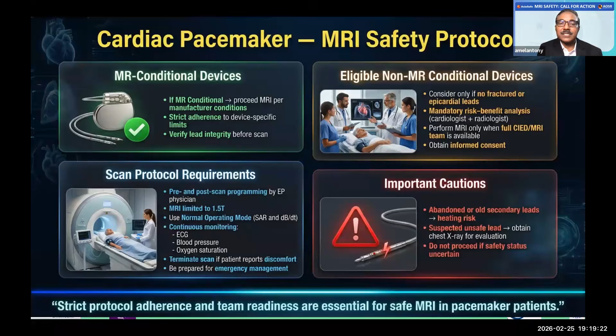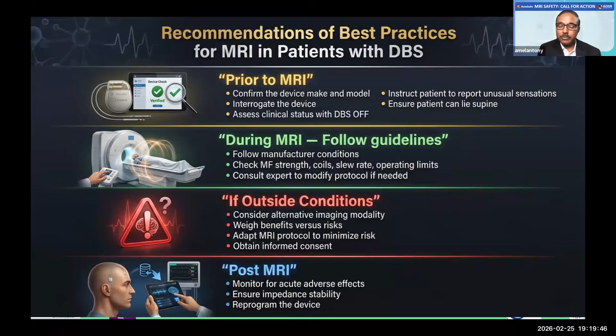And as mentioned again, if it is MR conditional, all the conditions specified by the vendor have to be met so that it's a safe scan for the patient as well as for the equipment. As far as DBS is concerned, the question always arises whether this particular scan is required, especially if it's the brain. Is there any other choice? And if it's for some other condition outside the brain, one should always consider an alternative imaging modality. And obviously one has to monitor for acute adverse effects and ensure that impedance stability is there.